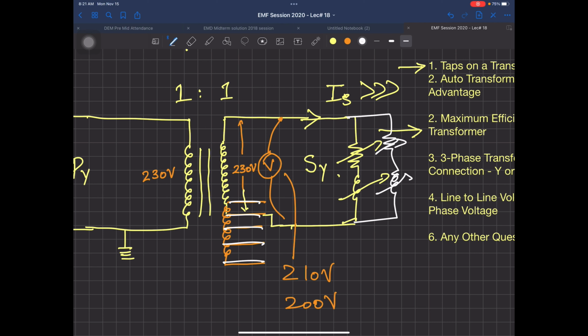This type of changer, in which you change the taps, is called an off-load tap changer. This means that first you disconnect all the load and then change the tap. Suppose in the summer season you have all the loads working at your homes: every house has 2 or 3 ACs, an iron working, a washing machine working. So the voltage is not sustaining. What the linemen near your house will do is connect it up till this point and then connect the load, but for this they have to disconnect the load first.